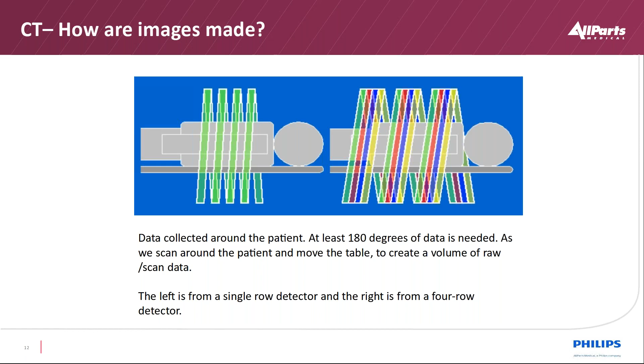So when you go from the left side, where you have a single row, to the multi-row side, we have to raise the amperage in the X-ray tube, aka the mA, to a higher level to have a dose per slice equivalent, to maintain that image quality. So as you can tell, when we go from 4 to 16 to 64, we have to have a higher amount of current in the X-ray tube to be able to produce that same consistency of image.